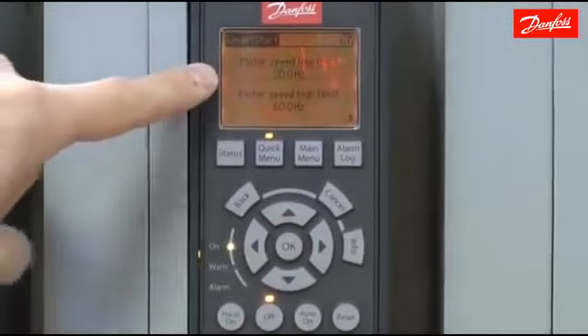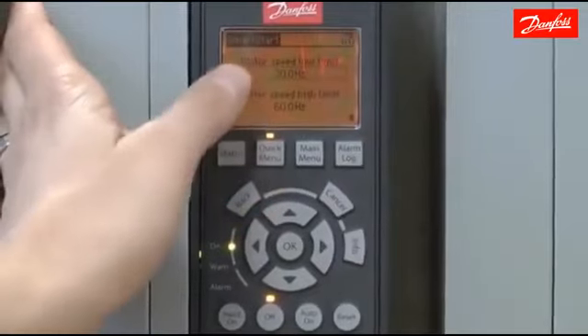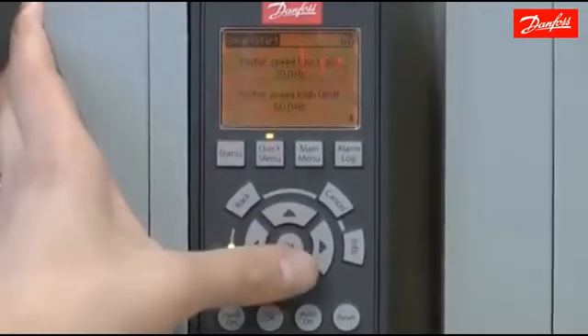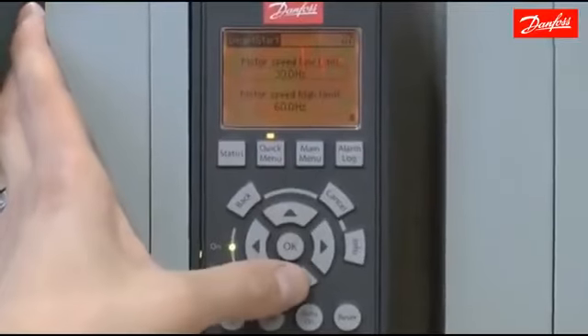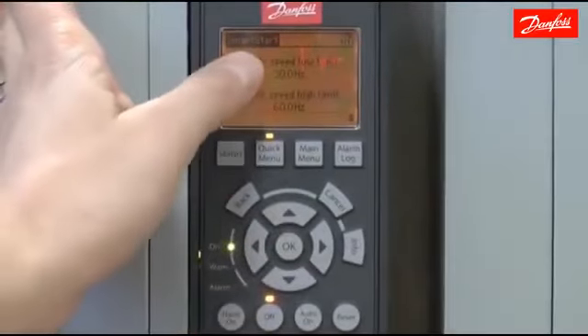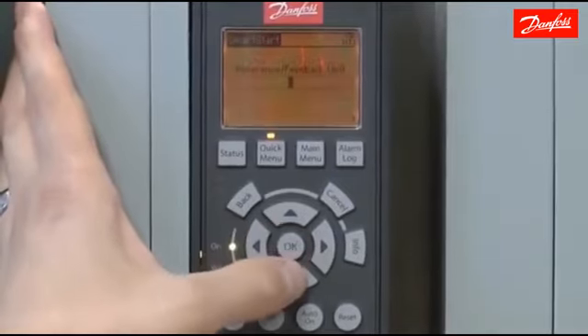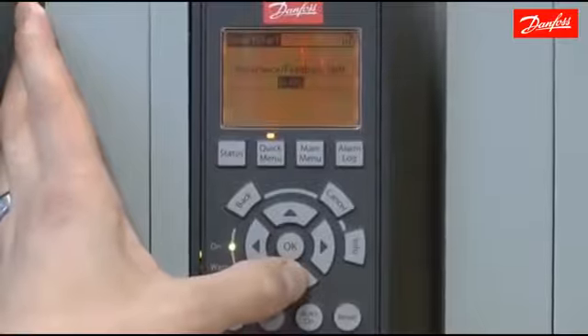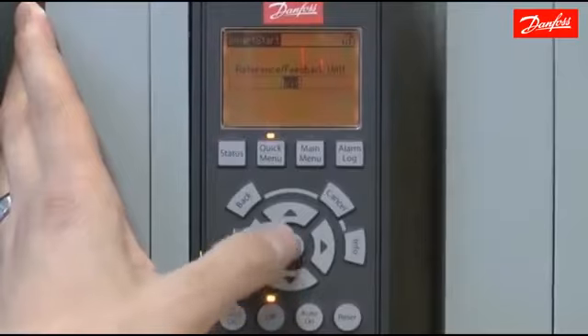type of pump that will be damaged for running below that speed. In any event, the motor will never run below the low limit. Same applies for the high limit. I'm going to operate the pump between 30 and 60 Hertz. The reference or feedback unit. There's multiple choices here. We're going to choose a feedback unit of PSI for our application.